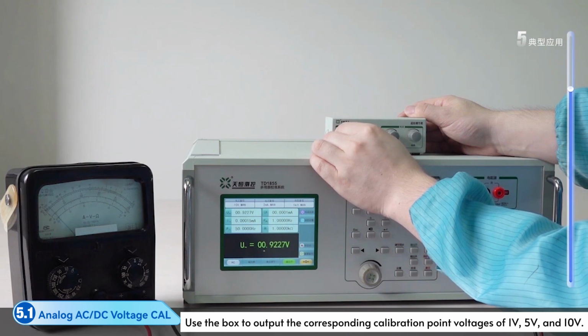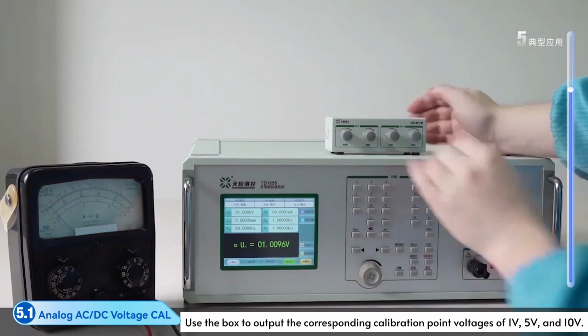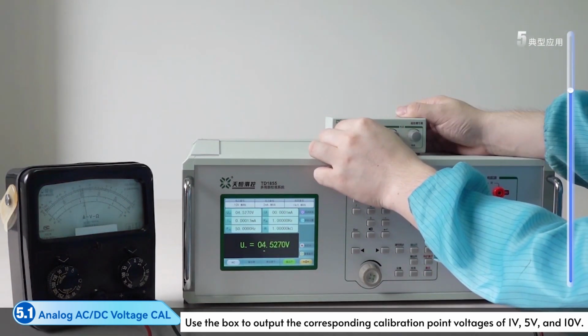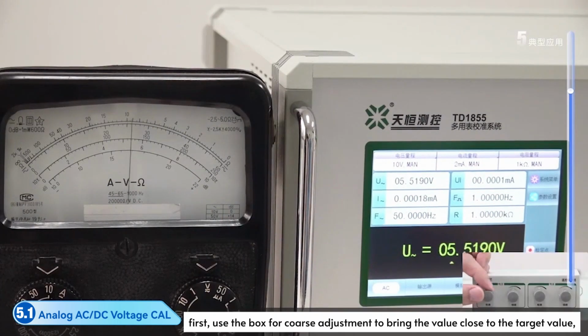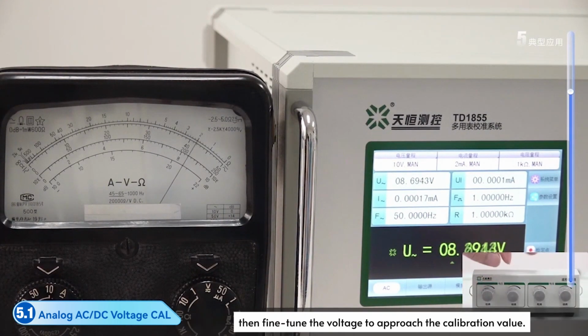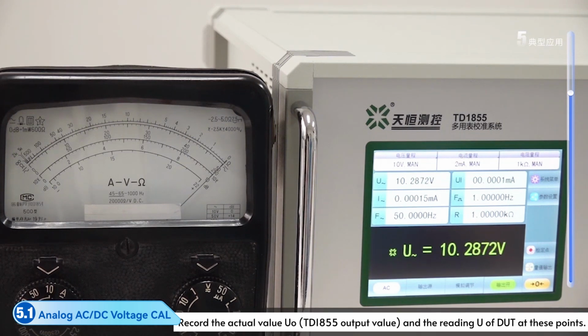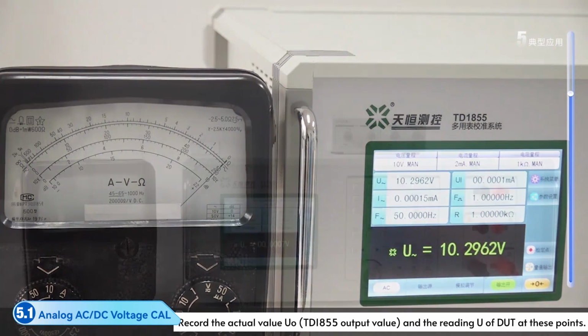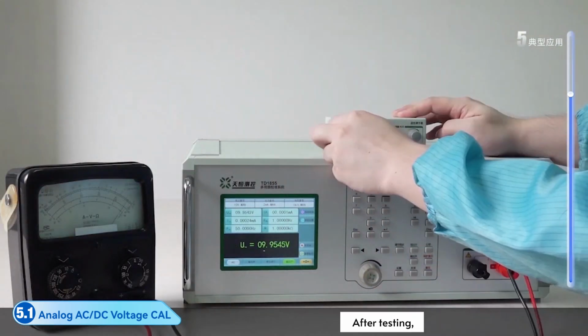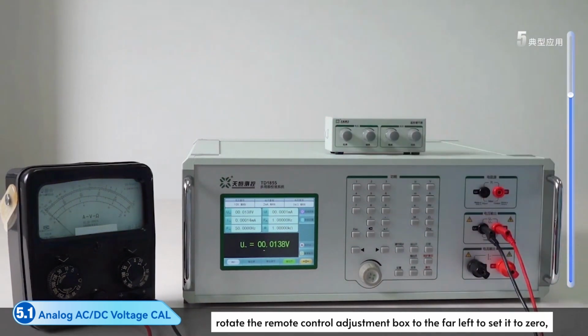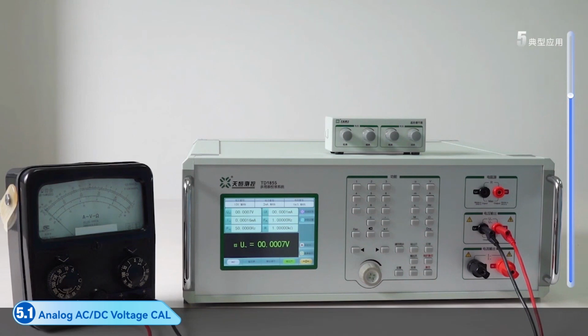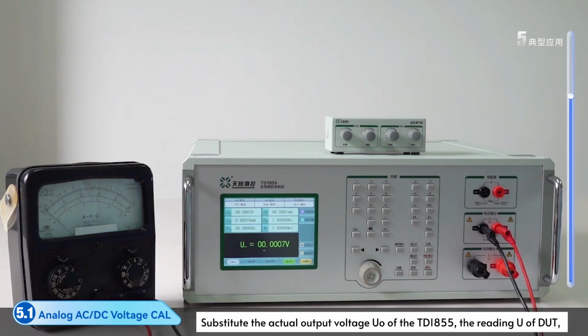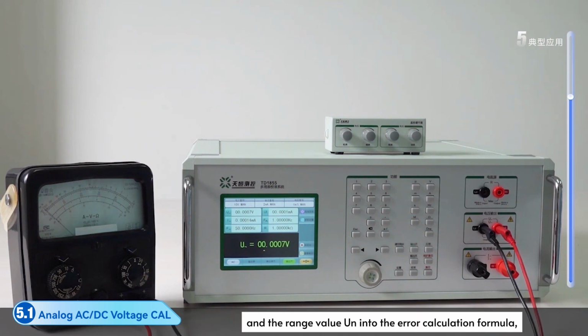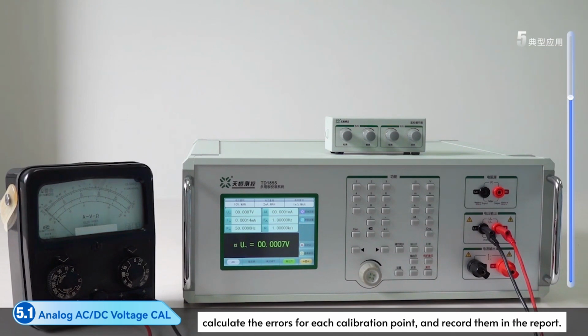Use the box to output the corresponding calibration point voltages of 1 volt, 5 volts, and 10 volts. During the output, use the box for coarse adjustment to bring the value close to the target value, then fine-tune the voltage to approach the calibration value. Record the actual value and the reading of DUT at these points. After testing, rotate the box knobs to the far left to set it to 0, then turn off the instrument. Substitute the actual output voltage of the TD1855, the reading of DUT, and the range value into the error calculation formula. Calculate the errors for each calibration point, and record them in the report.